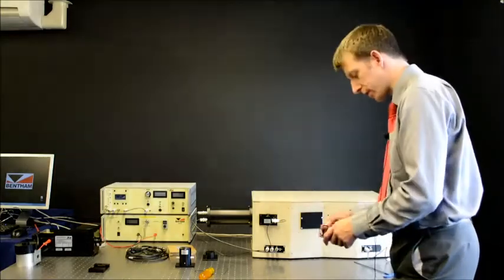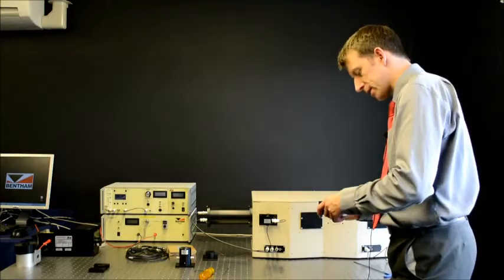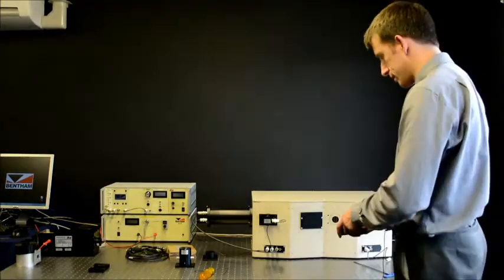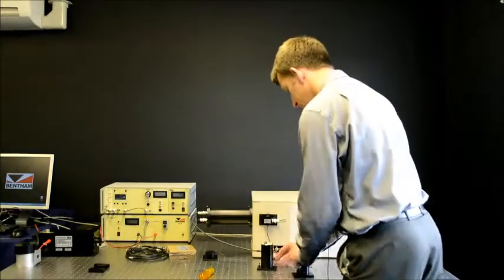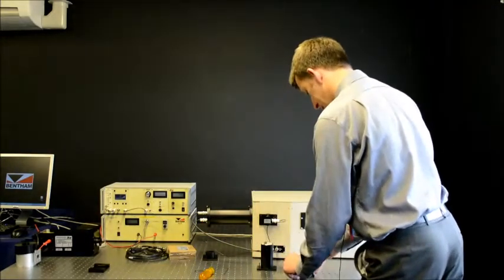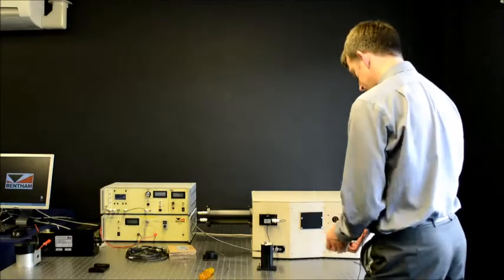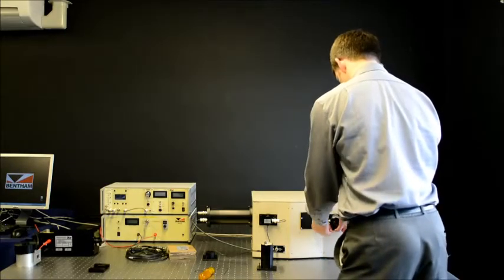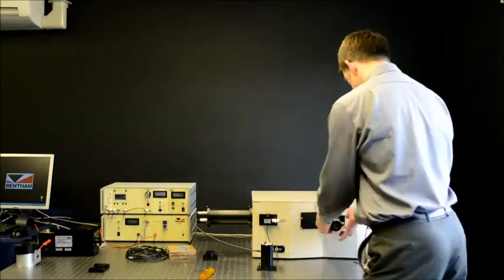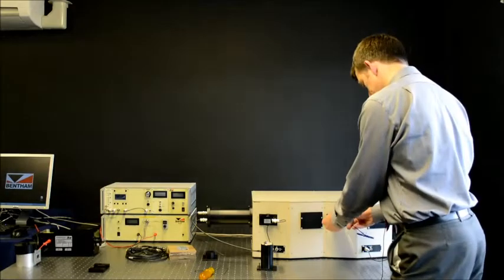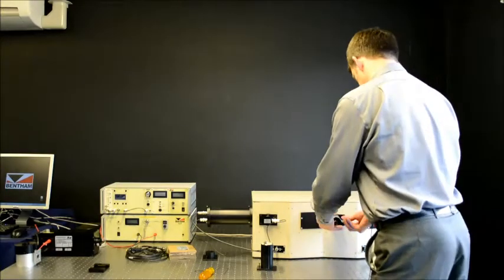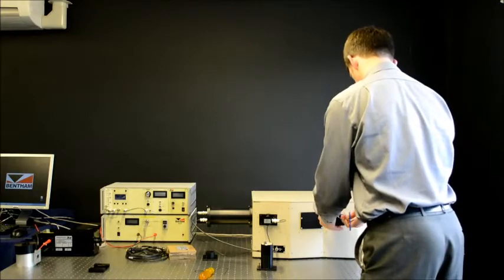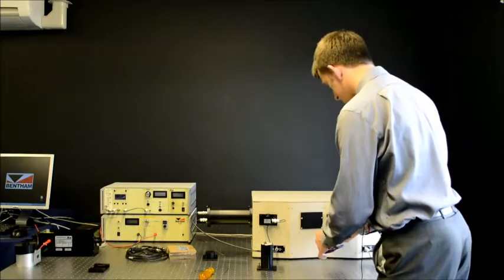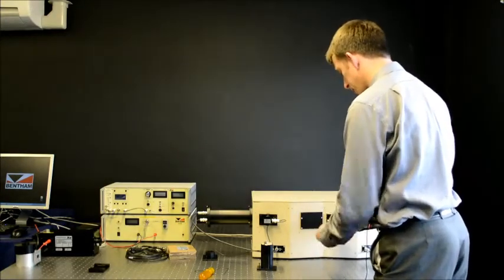Notice that an O-ring used to prevent light leaks has fallen out. We should make sure that stays in place. I will fit the lead sulfide detector then to the exit slit of the first monochromator. The lead sulfide detector has 3 connections.